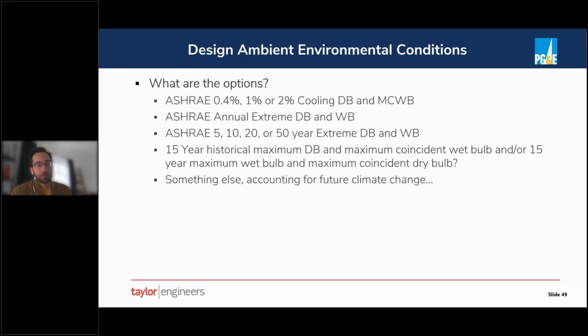For a data center, however, having exceedances 0.4% of the year could be particularly problematic, especially if those exceedances in turn lead to equipment failures or shutdowns that cause time out of service, which is very costly for a data center. So it's usually the case that for data centers, we use more conservative design conditions. And there are a whole bunch of options. Again, you could use the typical ASHRAE office building design conditions, but that's probably not a good idea. Another option would be to use the extreme dry bulb and wet bulb data that are also published by ASHRAE. But even that might be a little bit non-conservative because what is an extreme in one year may be exceeded in another year. So ASHRAE also publishes 5, 10, 20, and 50-year extreme dry bulb and wet bulb conditions for the climate zones for which you'll find data in the ASHRAE database.